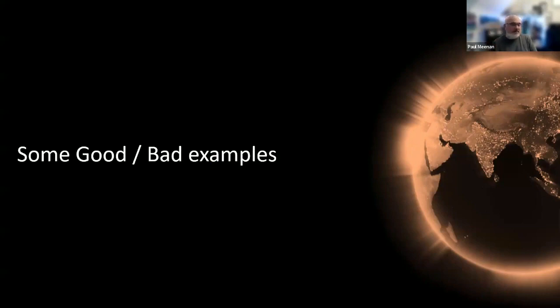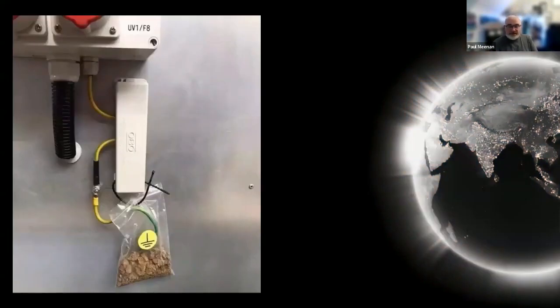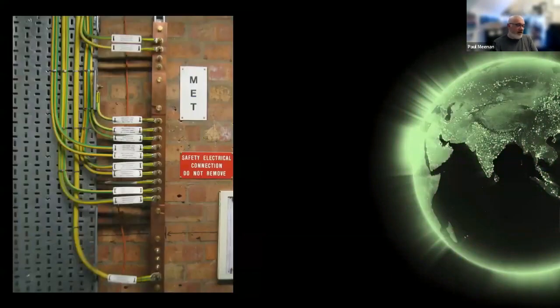I'm going to show you some good and bad examples. That's a terrible one. Obviously a wind up. I'm sure lots of people have seen this on social media. That's not earthing. That's called taking the mickey in England. But it's quite humorous to see that we can have some warped sense of humours. That is the main earth terminal, as you can see, with a label that says safety electrical connection, do not remove. That's an industrial cooling one, actually on the London Underground, and everything is labelled, heat shrunk, connected to its own terminal, and you have a drop link connection so that you can disconnect and separate the earthing so that you can test safely. So that's a good practice one.